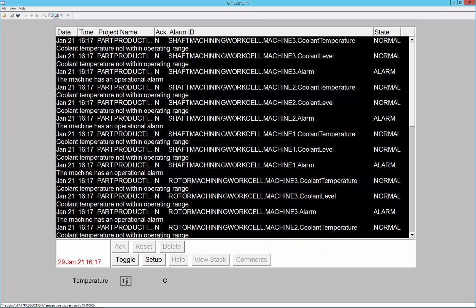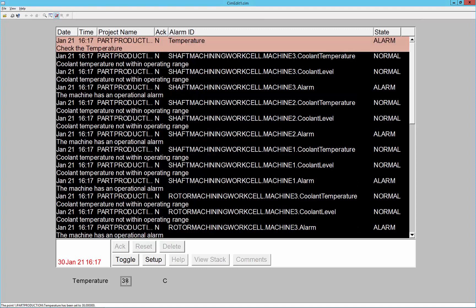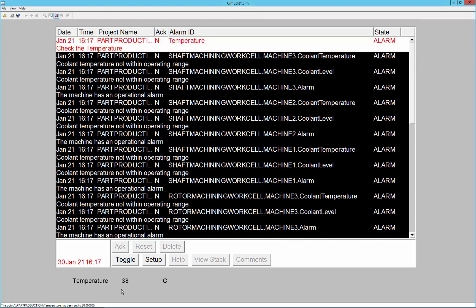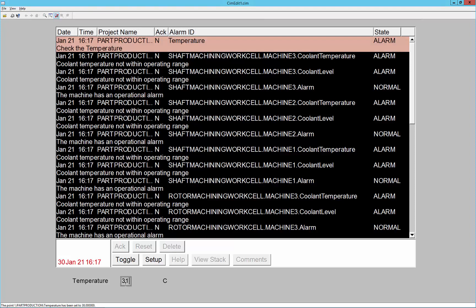And now I'm going to change the temperature into a high high state of 38 degrees. You can see when it's in a high high state, it's blinking according to that alarm class setting. If I bring it back down into another alarm state, but still an alarm but not high high, it goes to the high state.